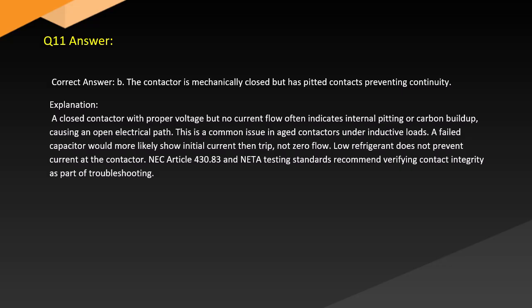Answer. Correct answer: B. The contactor is mechanically closed but has pitted contacts preventing continuity. Explanation. A closed contactor with proper voltage but no current flow often indicates internal pitting or carbon buildup, causing an open electrical path. This is a common issue in aged contactors under inductive loads.